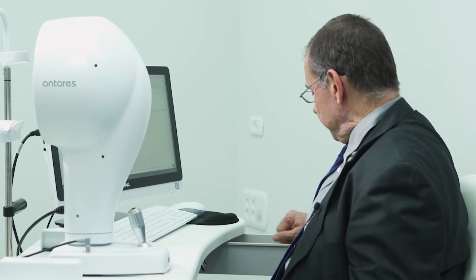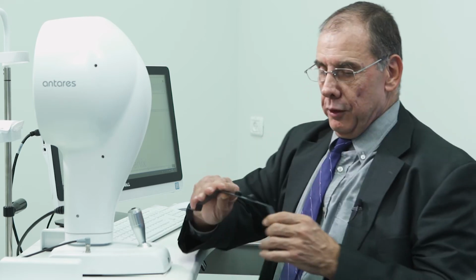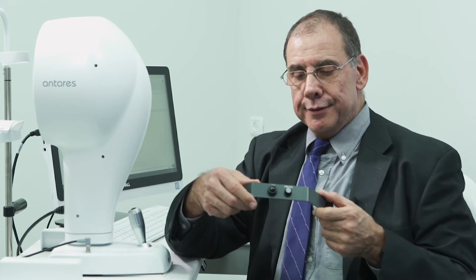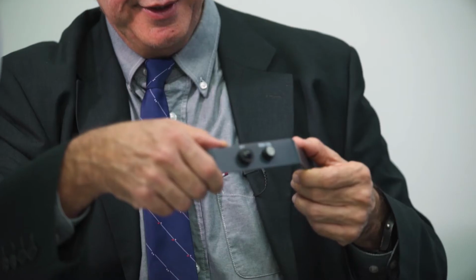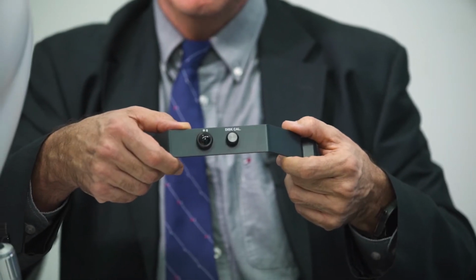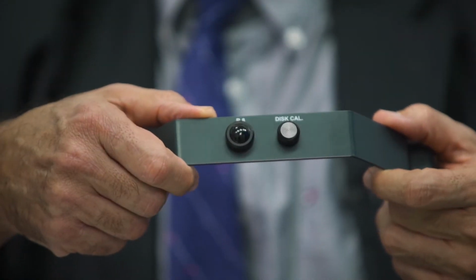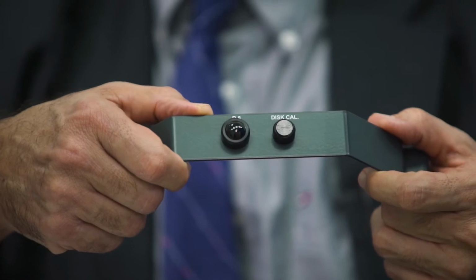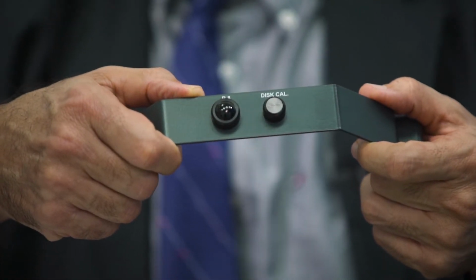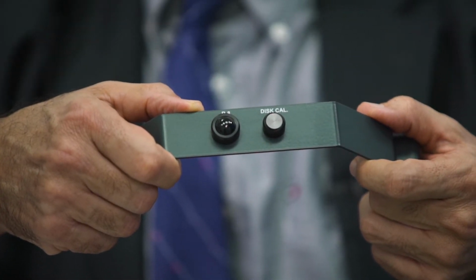You don't need to have a special technician to do it. You can do it by yourselves. And the calibration tool looks like this. It has a disc calibration and a radius 8 phantom eye or phantom cornea. And that's what we're going to basically do the calibration with.